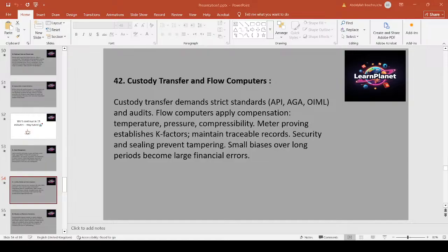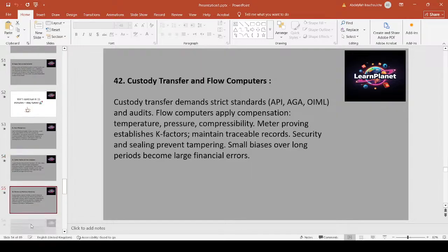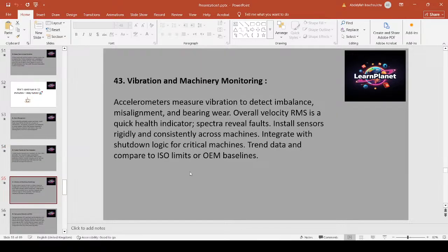Vibration and machinery monitoring. Accelerometers measure vibration to detect imbalance, misalignment, and bearing wear. Overall velocity RMS is a quick health indicator. Spectra reveal faults. Install sensors rigidly and consistently across machines. Integrate with the shutdown logic for critical machines. Trend data and compare to ISO limits and OEM baselines.